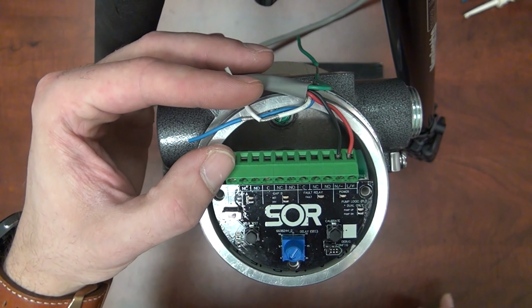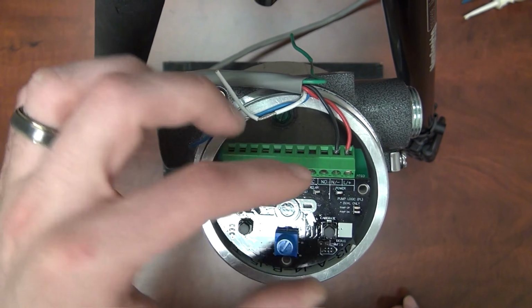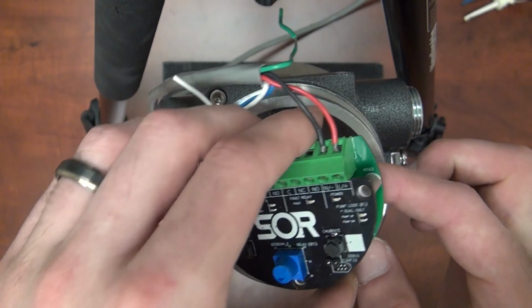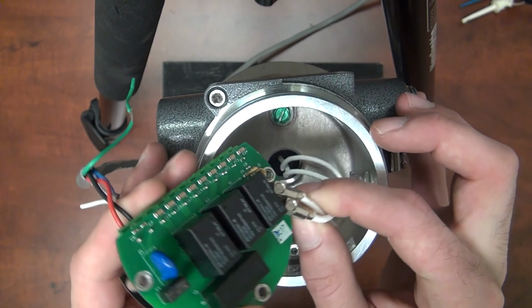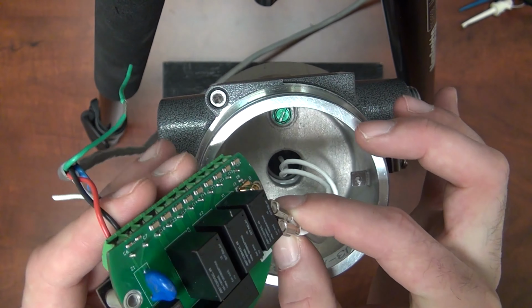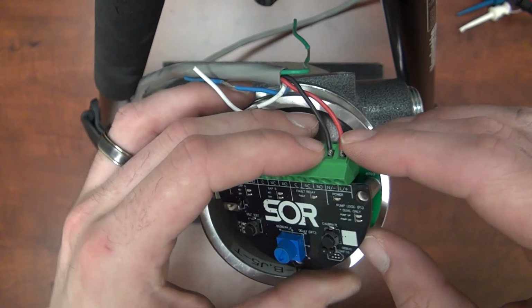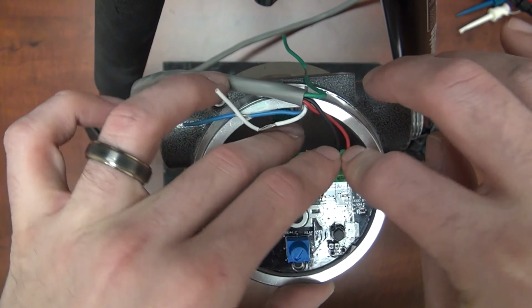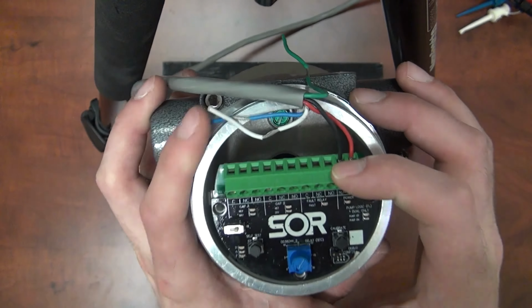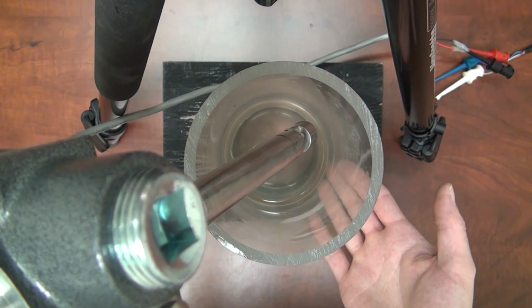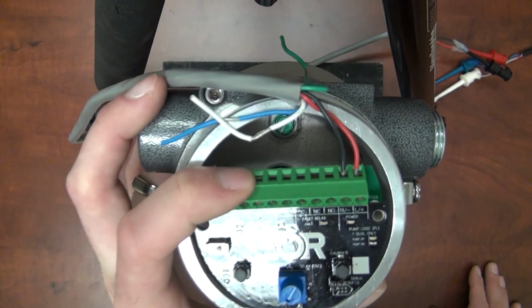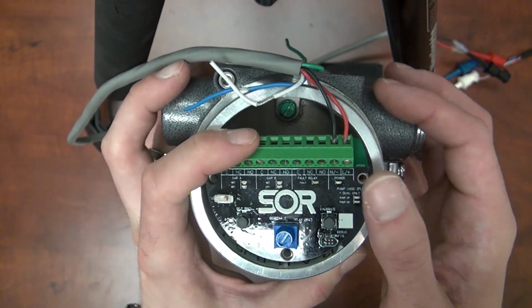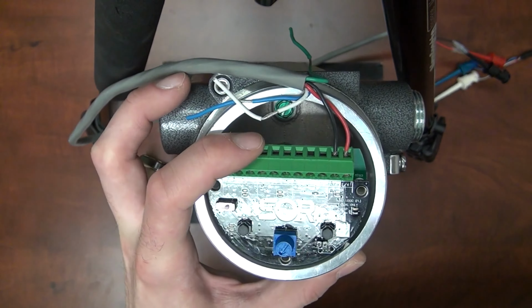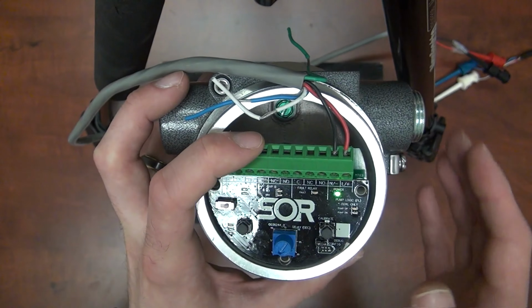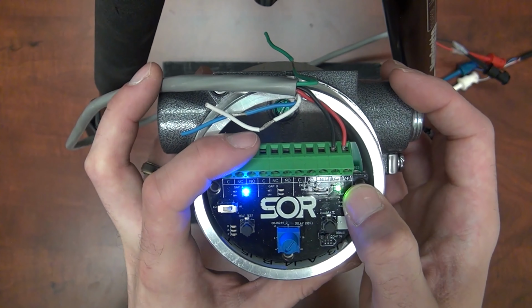Last, let's perform the wet calibration procedure. Start by removing the interface board and checking that the sensor is connected to the proper connection points on the back of our power board. Reassemble the boards back into the housing. First, we will submerge our probe into our process media, here being liquid water. Apply power to the device. The device will boot up in the normal operating state.